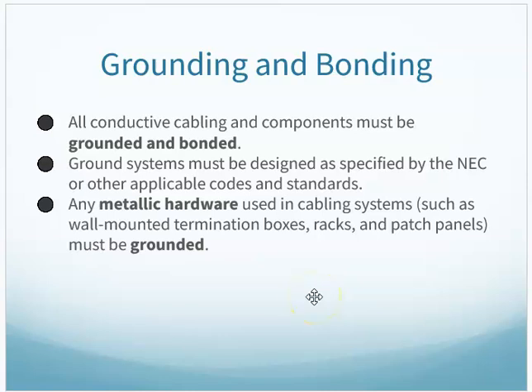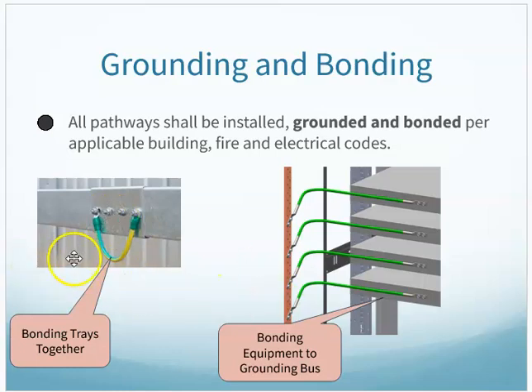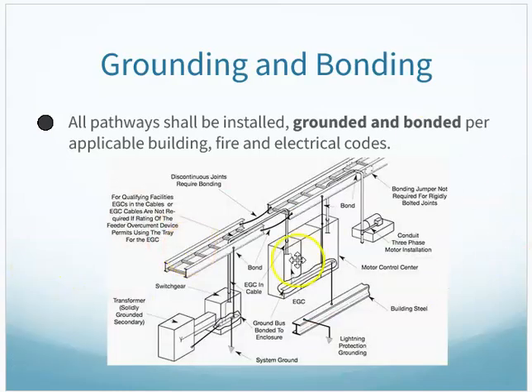Our equipment in our closets, we need to worry about grounding and bonding. Any metallic hardware should be grounded and bonded. Fiber optic doesn't have too much metallic hardware, but I might have shielding that needs to be dealt with. We'll look at that in just a second. So any of my trays, any of my equipment racks need to be properly grounded and bonded. Here's the standard and guide for how I do that.